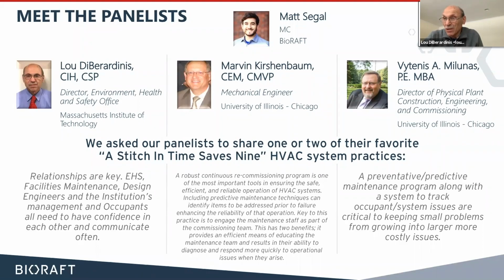What we've found in some cases were the wrong filters in place, filters that were dirty, systems that weren't calibrated as well as they should be. We have spaces not designed for occupancy that are now being occupied, like a storeroom that becomes an office, so it didn't have any ventilation to begin with. You really have to think of a holistic viewpoint when looking at the HVAC system.